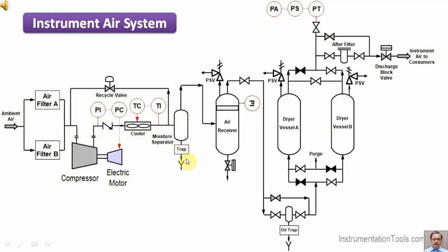The moisture in the air has been removed with the help of the moisture trap. Then the compressed air goes to the air receiver. From the air receiver it goes to the oil trap, from where the oil in the compressed air is removed. Then it passes through dryer vessel A and B, which work in sequence, one by one.